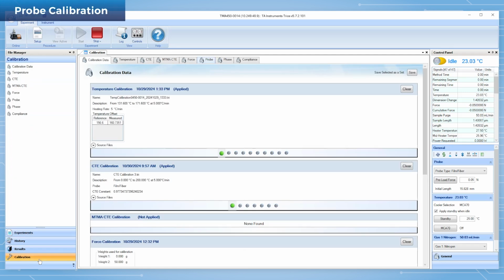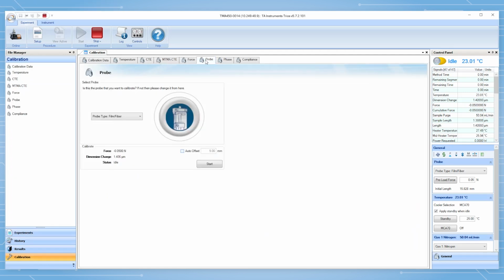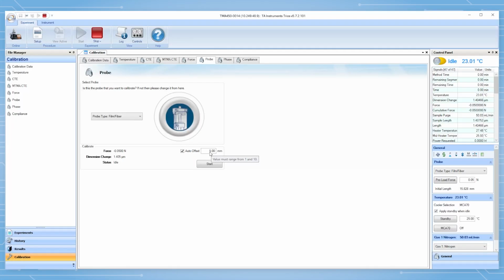The probe calibration compensates for various probe types. Therefore, probe calibration is performed every time a probe is changed. Specific to the film fiber probe, you will see that there is a checkbox for auto offset. The auto offset calibration must be completed during the first use of the film fiber probe. By toggling the auto offset checkbox on, this will enable additional measurement during the probe calibration. This calibration will compensate for the thickness of the stage platform and the upper portion of the probe.